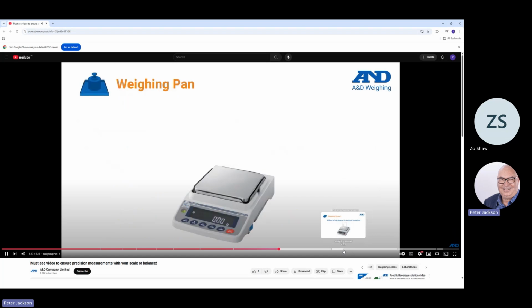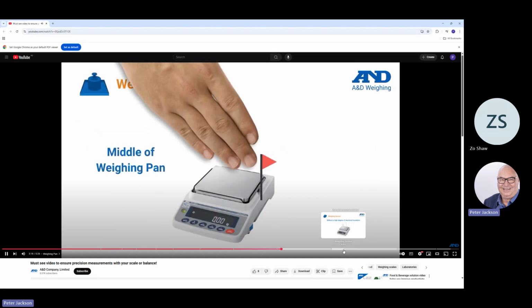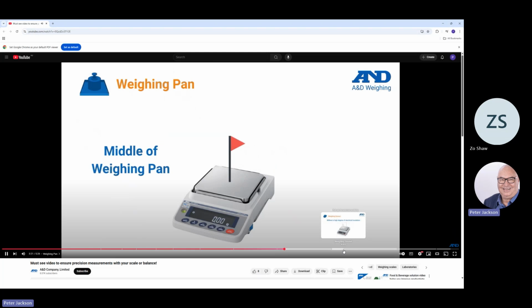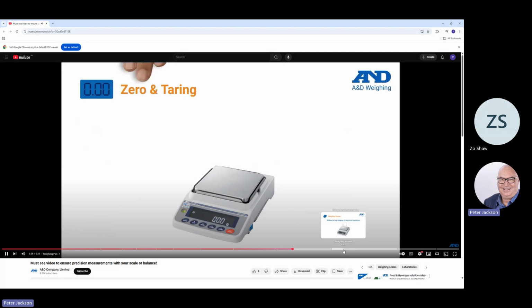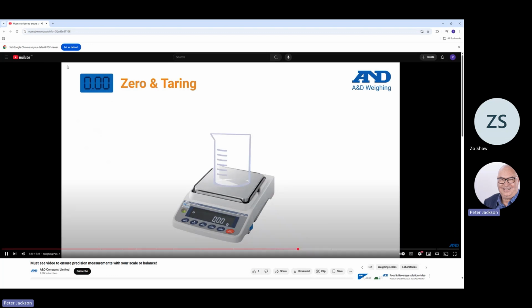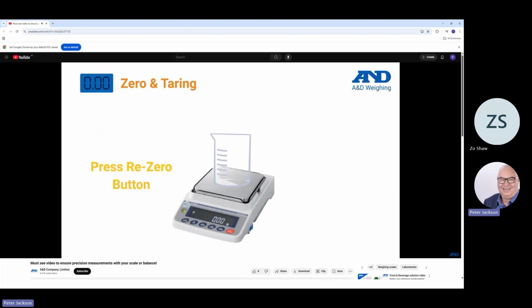Samples and/or weighing vessels should be placed in the middle of the weighing pan to prevent corner load errors. We minimize this chance for error with our high-quality engineered pan design. You should zero the balance regularly before placing anything on the pan, as this will provide maximum capacity.